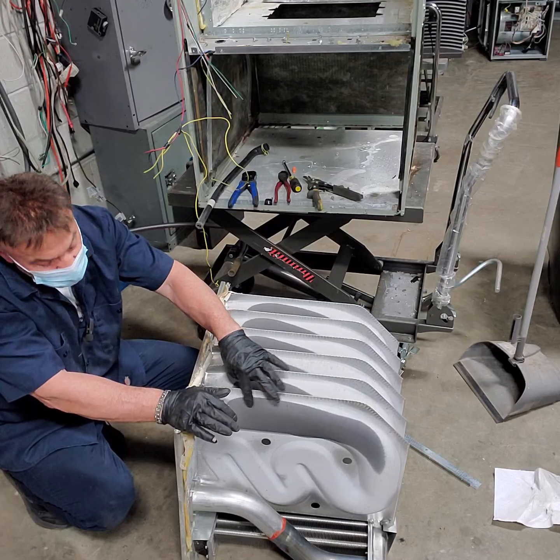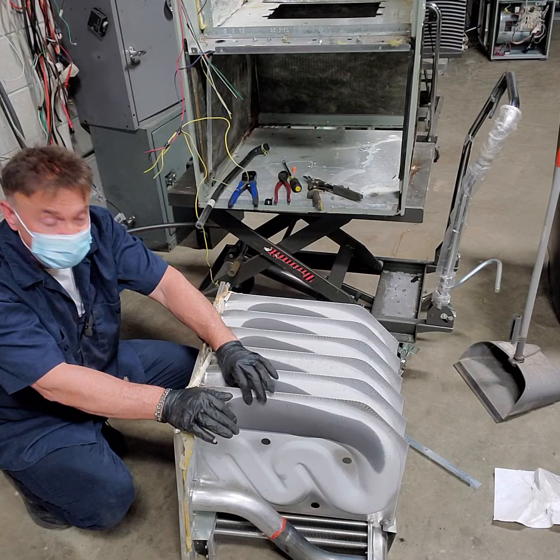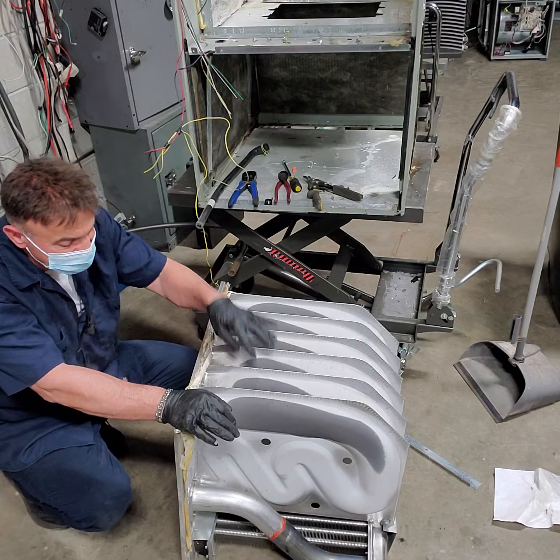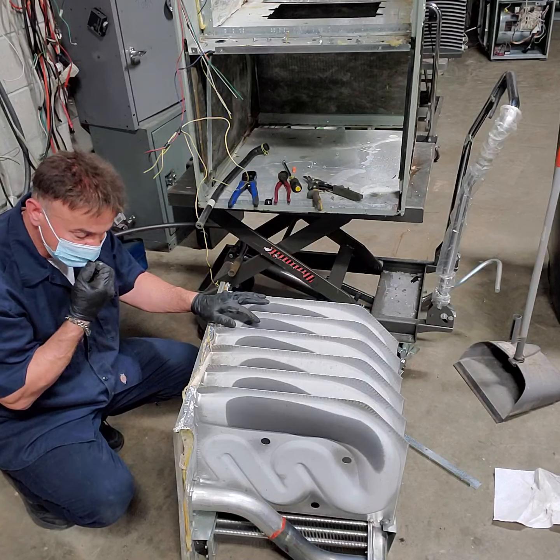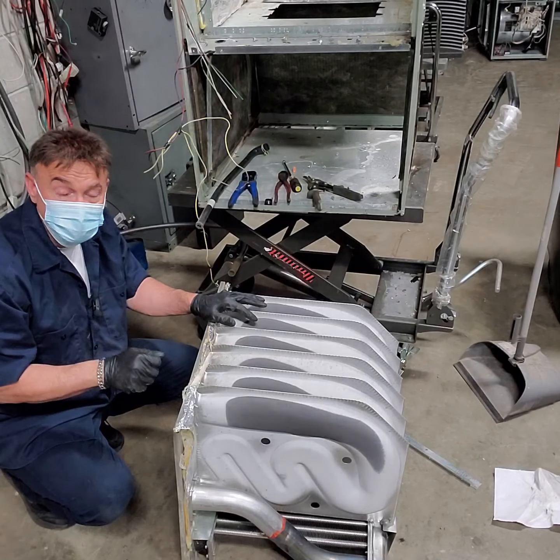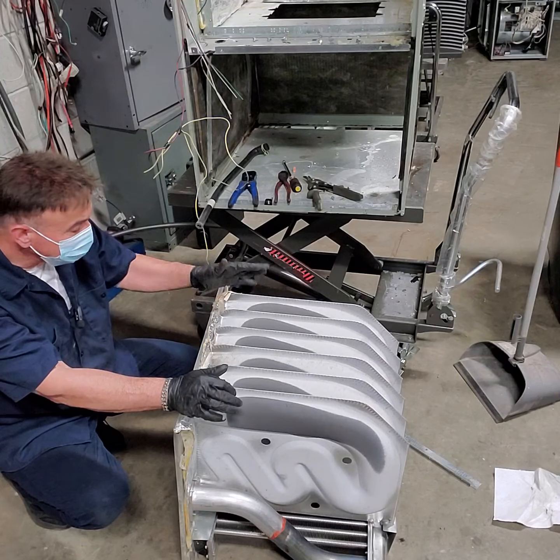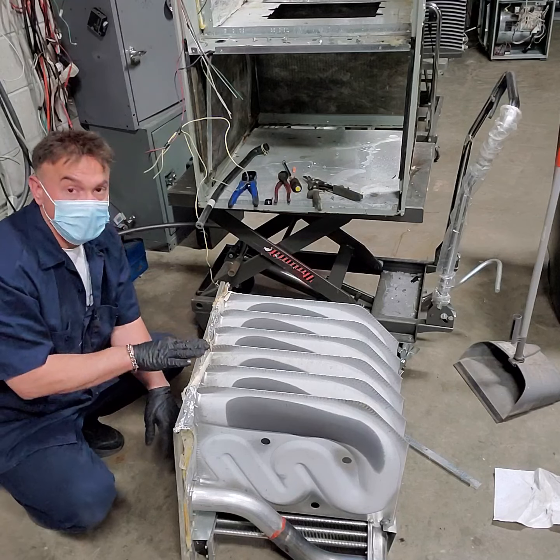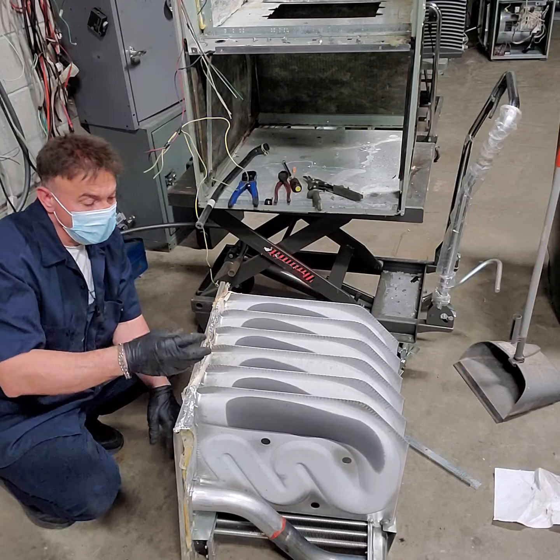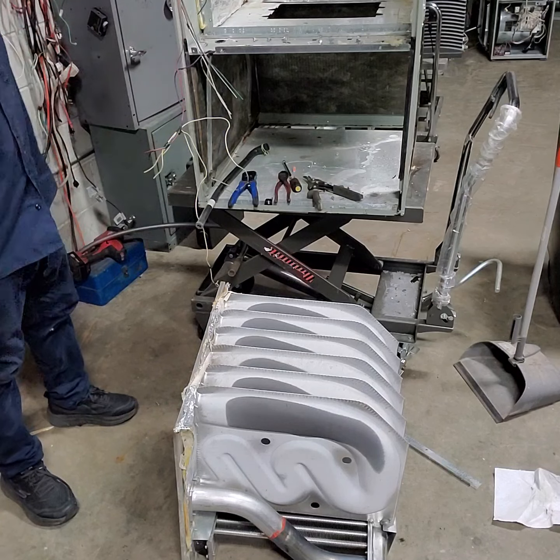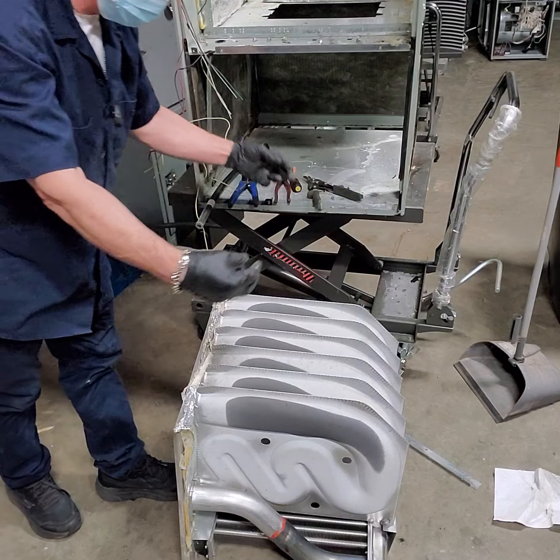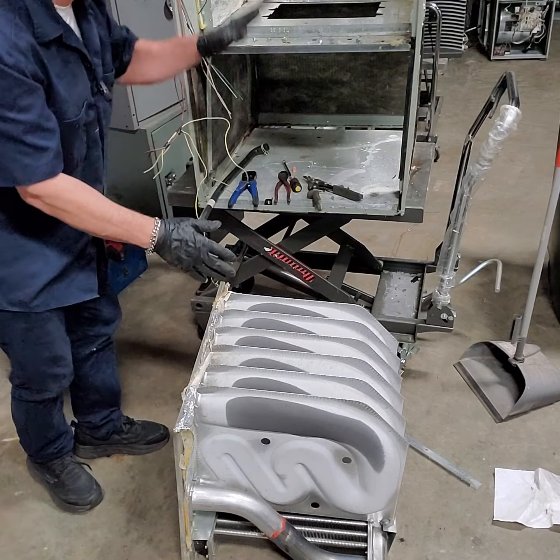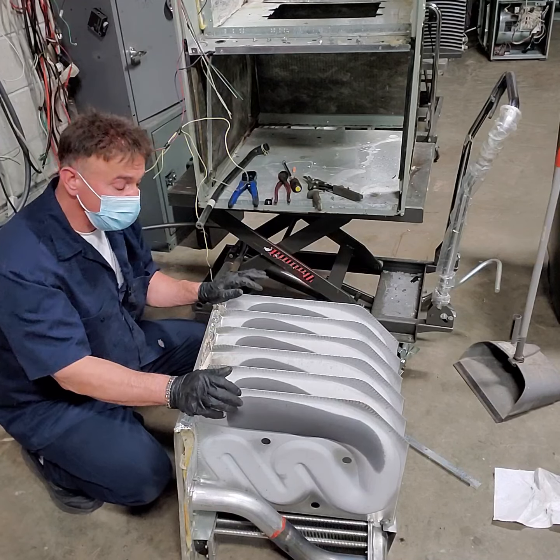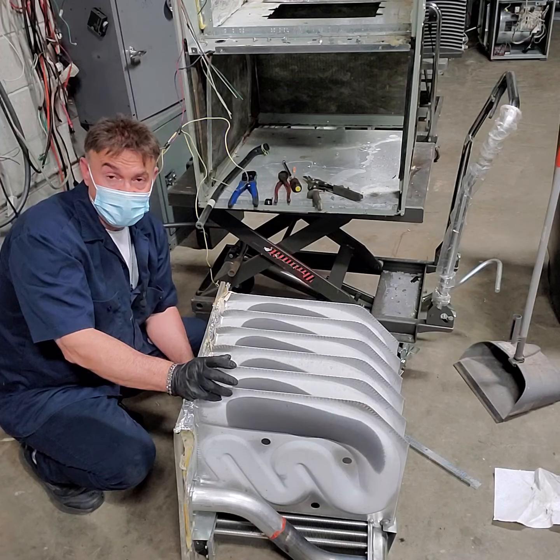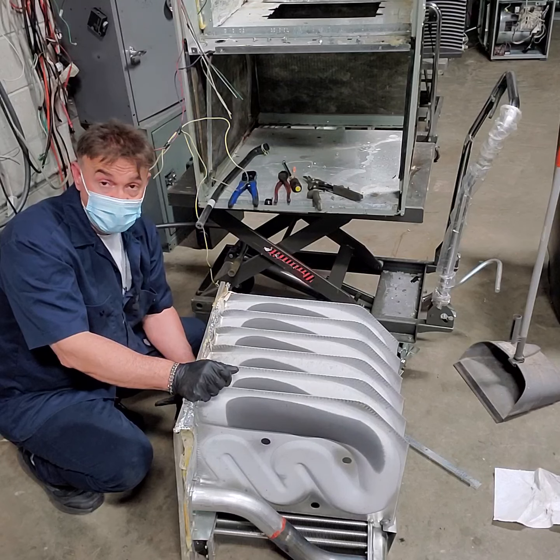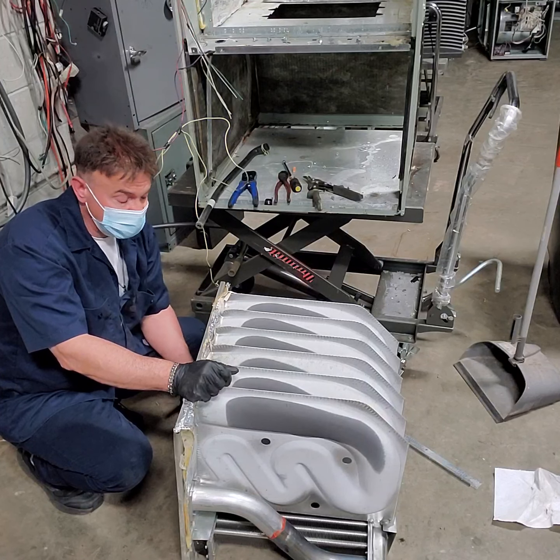I believe this could look orange. You know how when you heat metal, it can look really orange at some point. Why? Again, because the burners were not adjusted. And in a case like this, I keep touching this, I hate it. In a case like this, if you put your thermometer on the supply, right on top of the furnace, let's say you have a duct on top of the furnace, I guarantee you the temperature of the air is more than 130. I have seen it sometimes be 180.